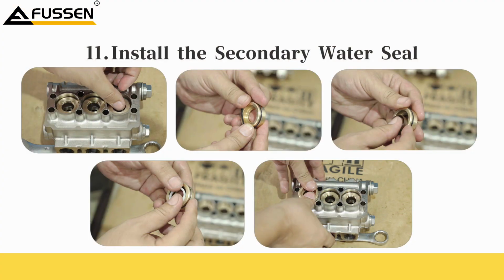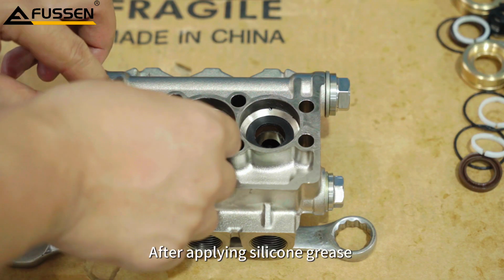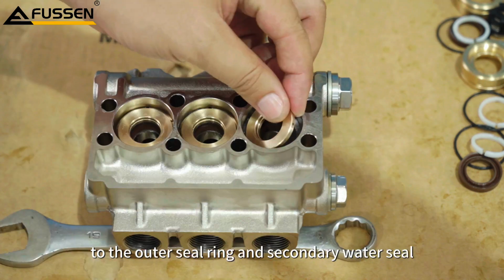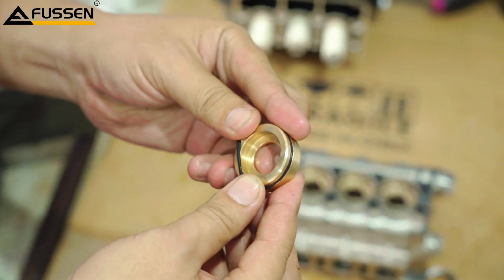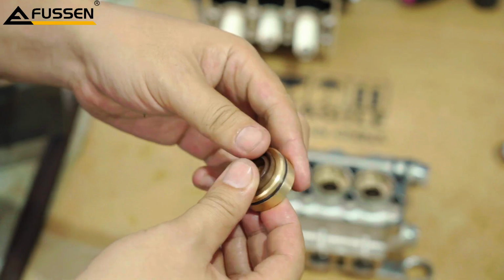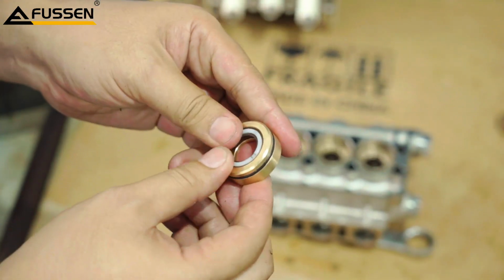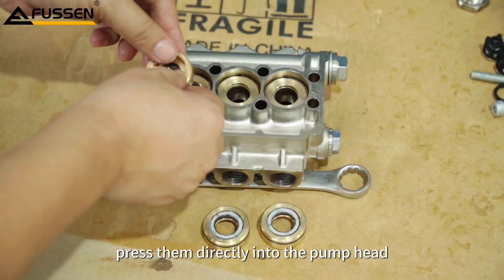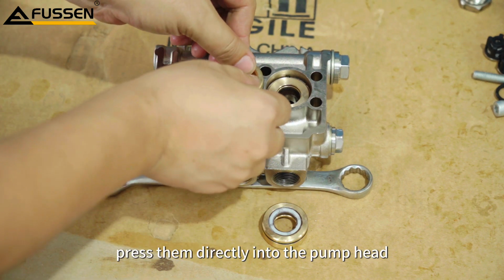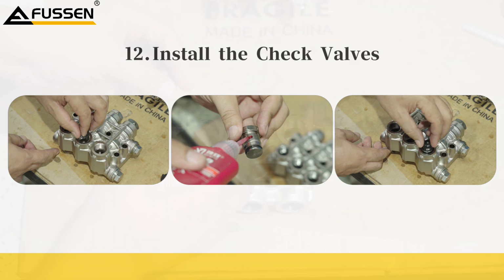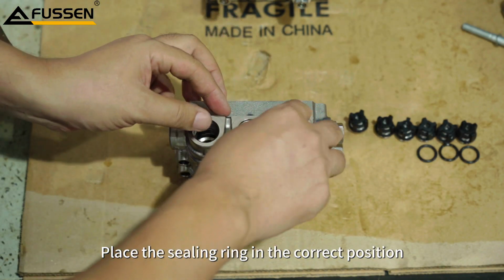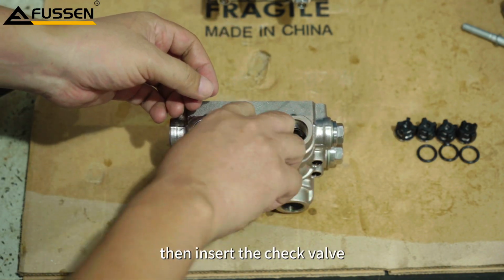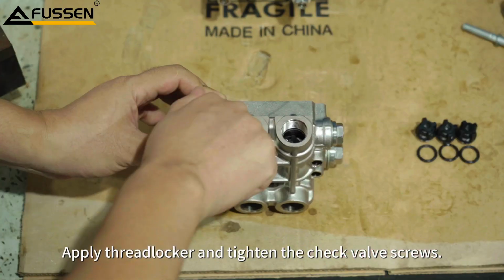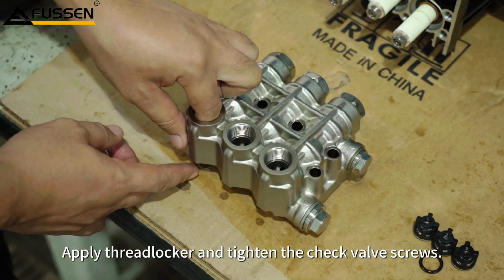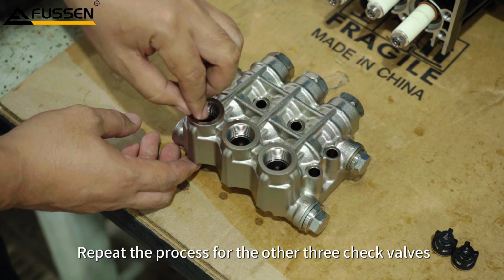Installing the secondary water seal. After applying silicone grease to the outer seal ring and secondary water seal, press them directly into the pump head. Installing the check valves. Place the sealing ring in the correct position, then insert the check valve. Apply thread locker and tighten the check valve screws. Repeat the process for the other 3 check valves.